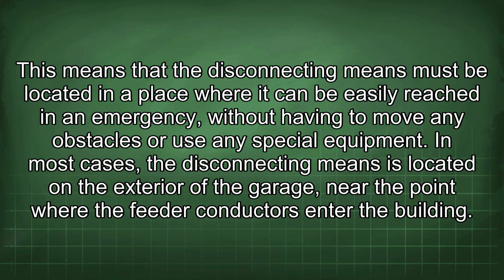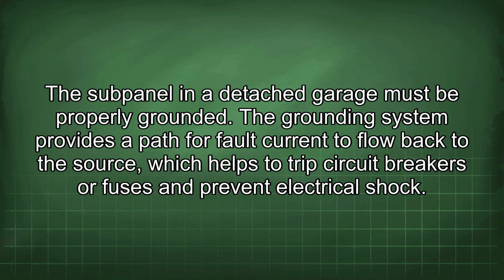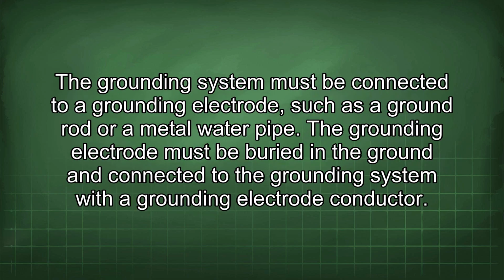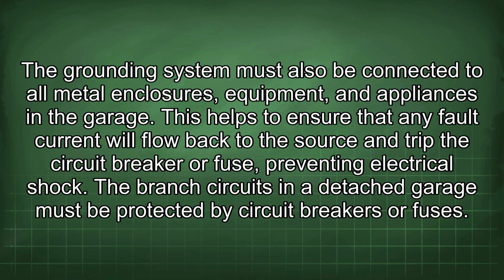The subpanel in a detached garage must be properly grounded. The grounding system provides a path for fault current to flow back to the source, which helps to trip circuit breakers or fuses and prevent electrical shock. The grounding system must be connected to a grounding electrode, such as a ground rod or a metal water pipe. The grounding electrode must be buried in the ground and connected to the grounding system with a grounding electrode conductor. The grounding system must also be connected to all metal enclosures, equipment, and appliances in the garage. This helps to ensure that any fault current will flow back to the source and trip the circuit breaker or fuse, preventing electrical shock.